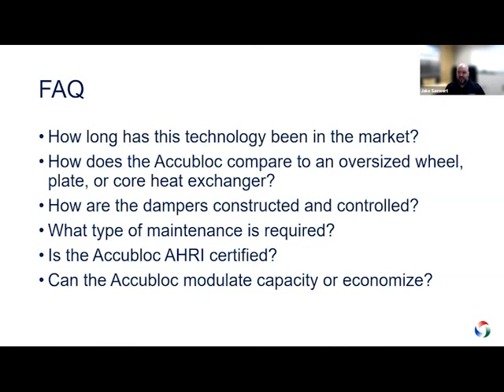From a maintenance standpoint, there's not a lot you need to do with the heat exchanger because you're going to do pre-filtration on both sides on the inlets. So you're going to be cleaning the air, but it can be cleaned like any other enthalpy wheel with water or steam. And then the dampers over time, just making sure that they're functioning correctly and the motor's operating like it should. The ACCUBLOC is not AHRI certified, and it's just because there's no category for it here in the United States.